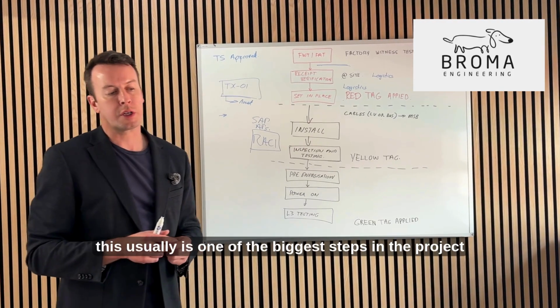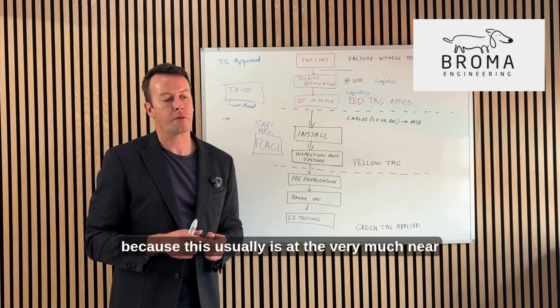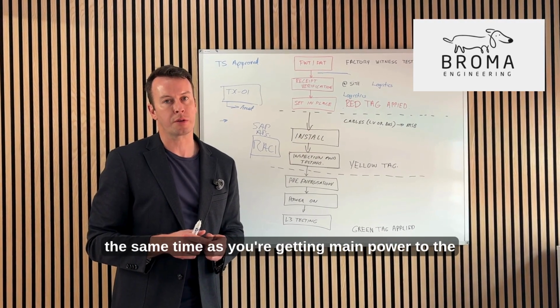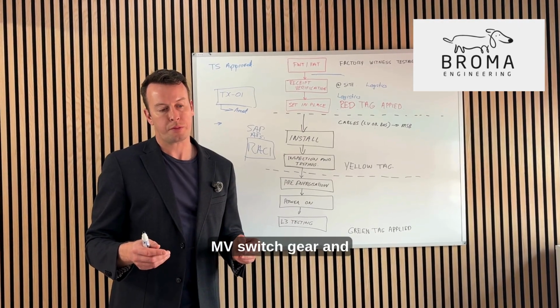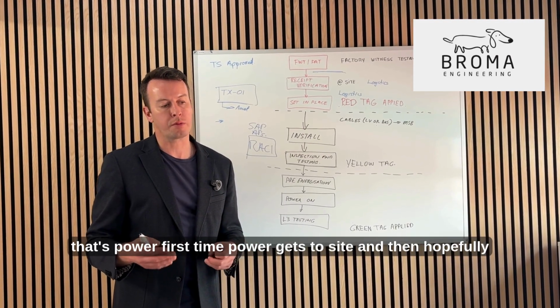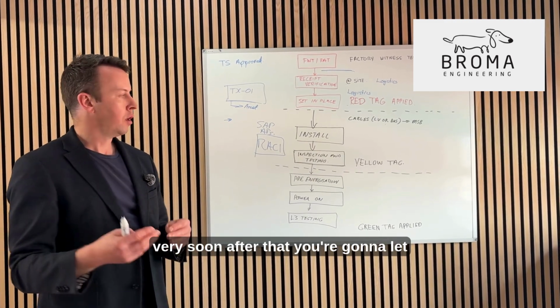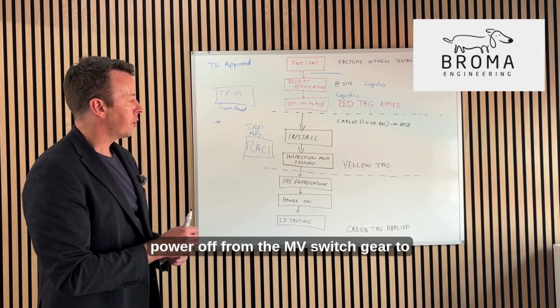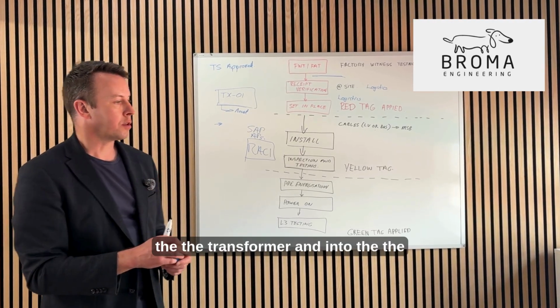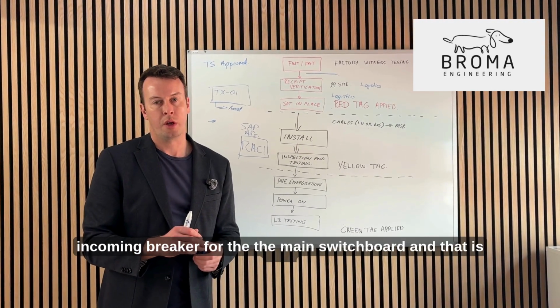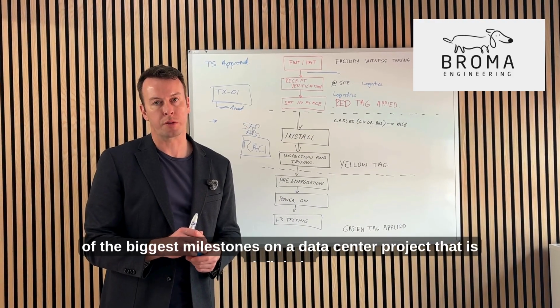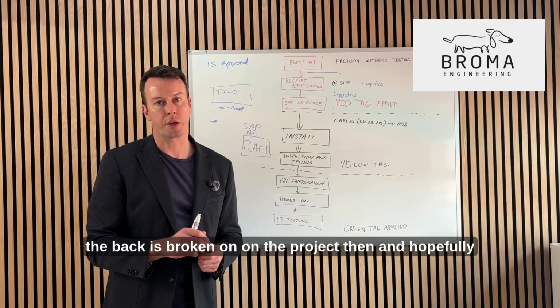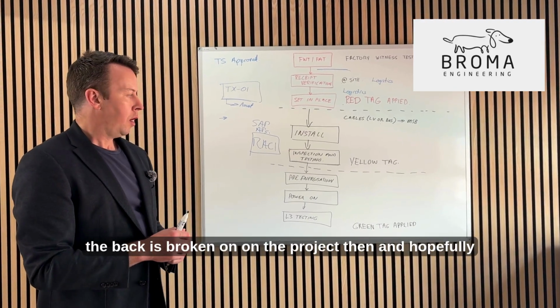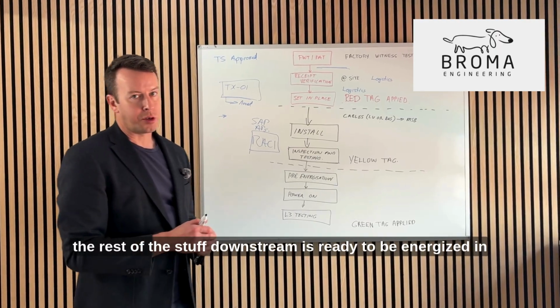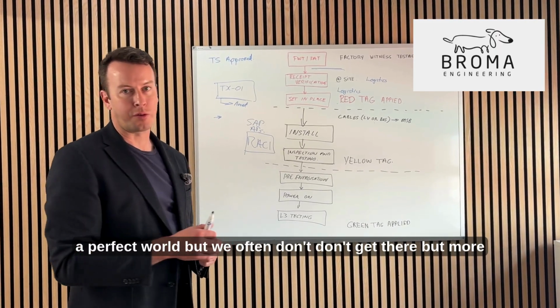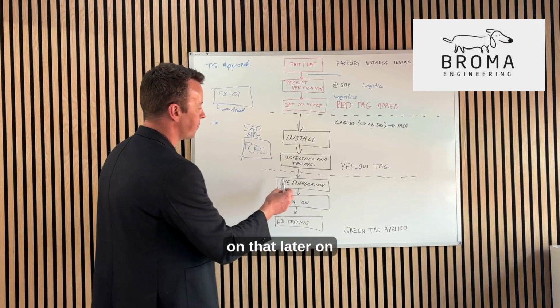And this usually is one of the biggest steps in the project, because this usually is at the very much near the same time as you're getting main power to the MV switchgear, and that's first time power gets to site, and then hopefully very soon after that you're going to let power off from the MV switchgear to the transformer and into the incoming breaker for the main switchboard. And that is one of the biggest milestones on a data center project. That is definitely the back is broken on the project then. And hopefully the rest of the stuff downstream is ready to be energized in a perfect world, but we often don't get there. But more on that later on.